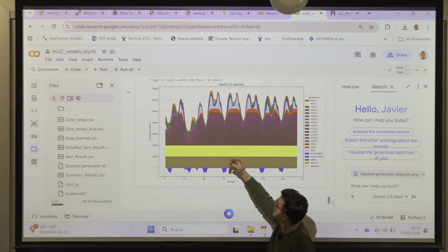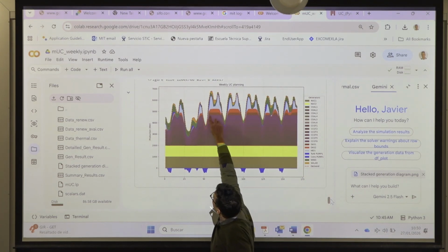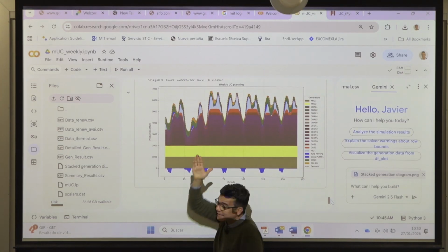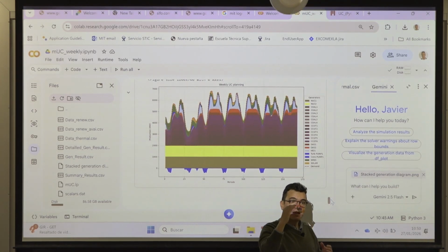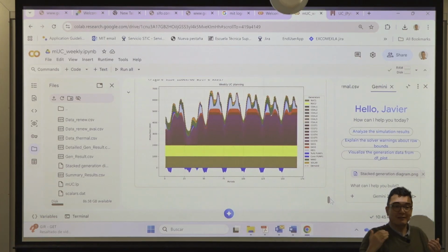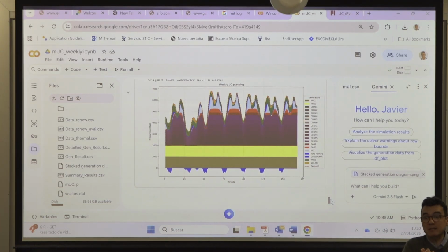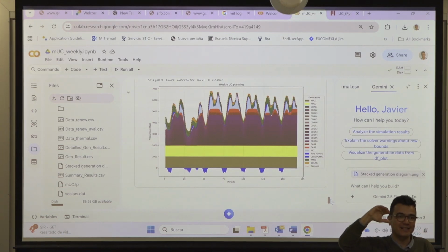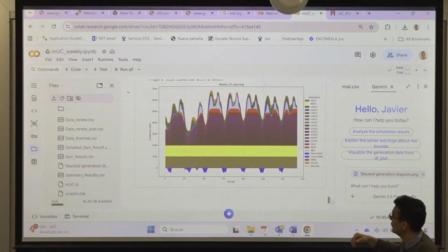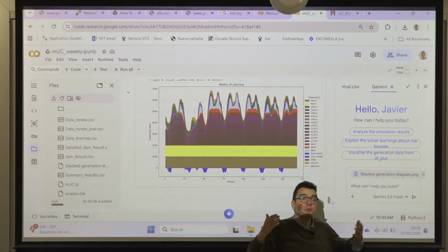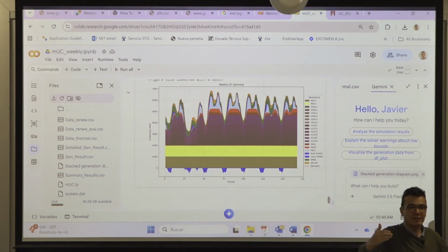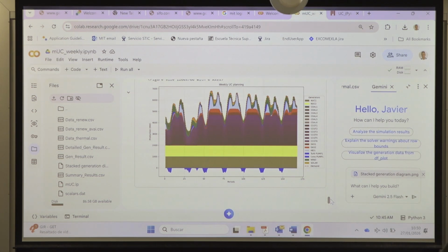This is why we have this little slice here, because the demand is increasing so much, the combined cycle power plants have a maximum ramp capability, and they're not able to follow the demand as fast as it is changing. So I need to use water in these hours, despite not being so optimum in the sense of avoiding the cost, but it's the only feasible solution.